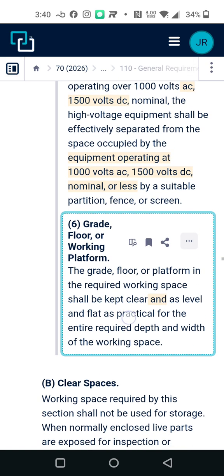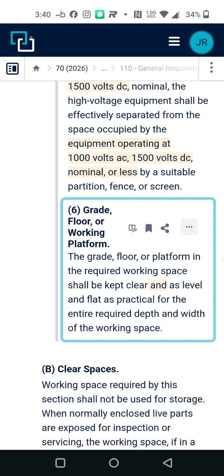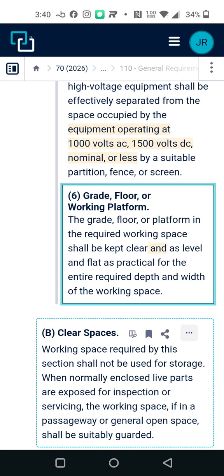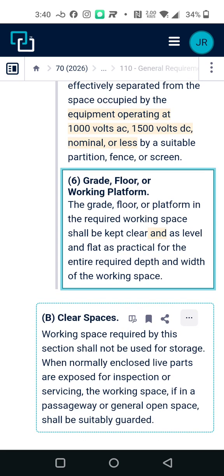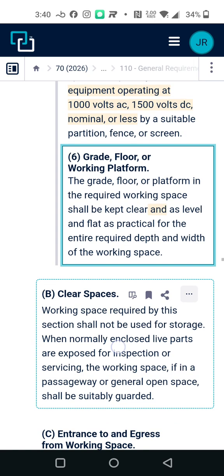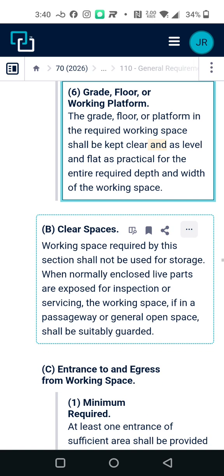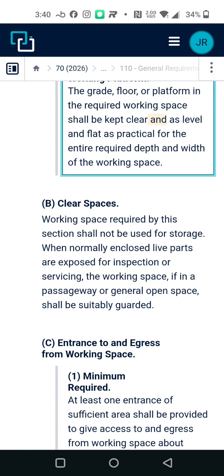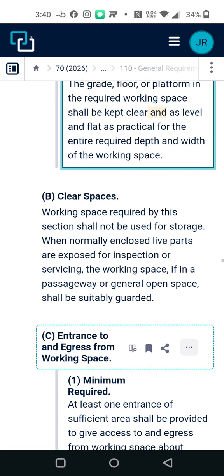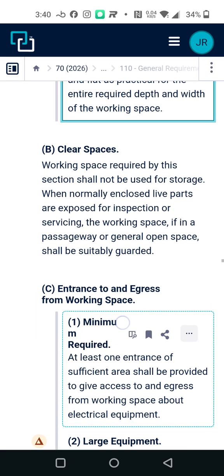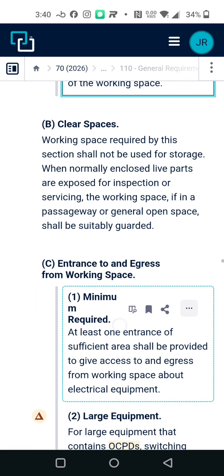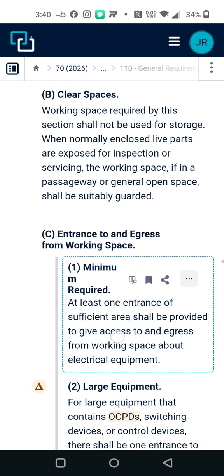Grade, floor, platform. The grade, floor, or platform in the required working space should be kept clear and level and flat, as practical, for the entire required depth and width of the working space. Clear spaces. The working space required by the section should not be used for storage. When normally enclosed live parts are exposed for inspection or service in the working space, if in any passageway or general open space, it should be suitably guarded.